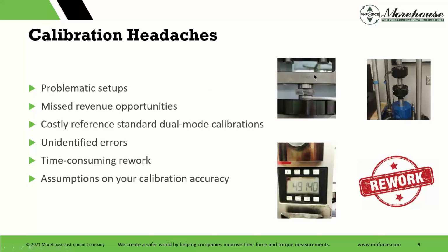And I'm looking for my pen, but if I don't have it, that's fine. But these setups here are problematic, right? They can be problematic. This one, if I'm calibrating a button load cell using this method, just a flat plate, I'm going to get a different result, maybe not as repeatable, if I use adapters that are better for centering. This dynamometer, we're going to talk about this here. It's supposed to read 50,000 pounds of force, and it's 860 pounds out.